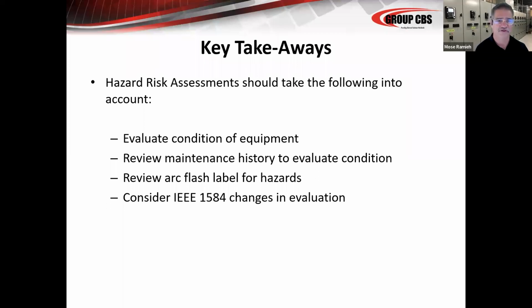Any major changes, like the utility putting a new, larger transformer outside your building, that's going to necessitate a review of your arc flash study, because if they put a lower impedance transformer outside your facility, your arc flash study needs to be adapted to that.